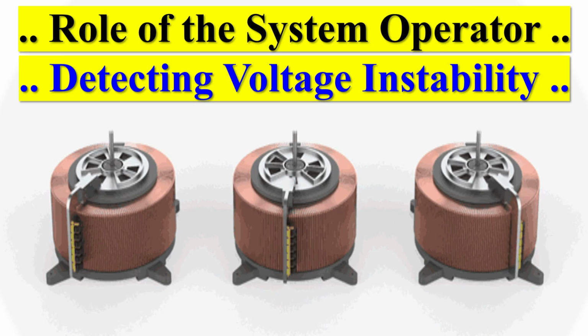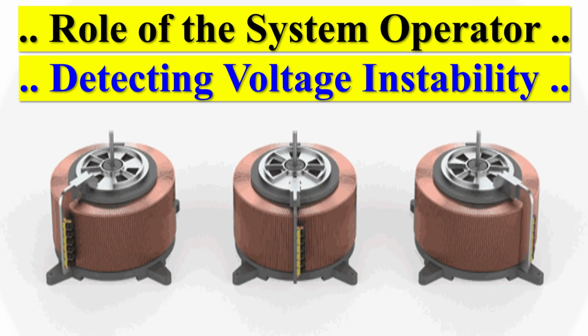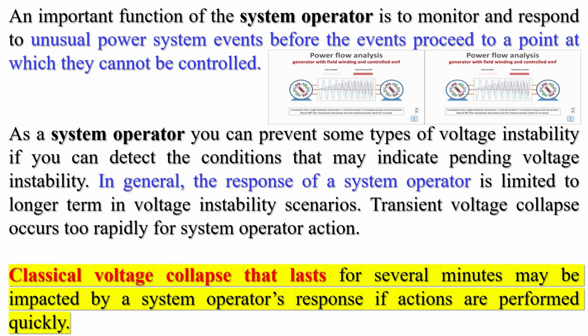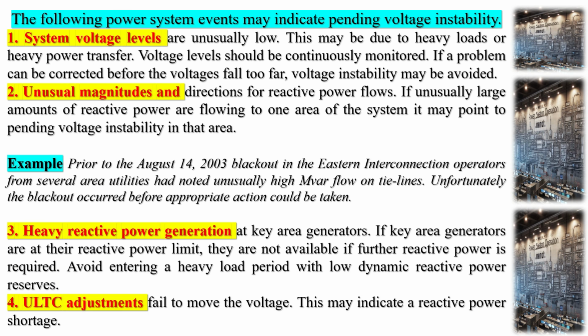Role of the system operator in detecting voltage instability. An important function of the system operator is to monitor and respond to unusual power system events before the events proceed to a point at which they cannot be controlled. As a system operator, you can prevent some types of voltage instability if you can detect the conditions that may indicate pending voltage instability. In general, the response of a system operator is limited to longer-term voltage instability scenarios. Transient voltage collapse occurs too rapidly for system operator action. Classical voltage collapse that lasts for several minutes may be impacted by a system operator's response if actions are performed quickly. The following power system events may indicate pending voltage instability.